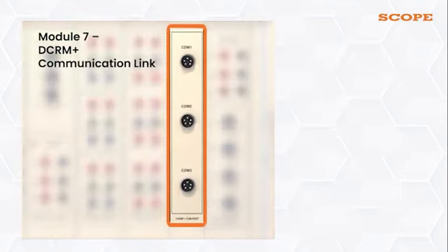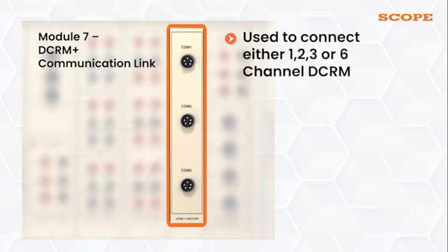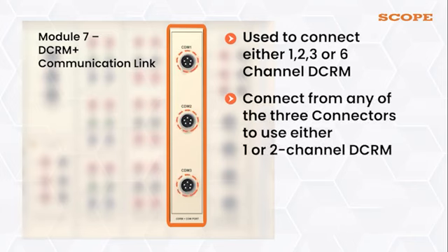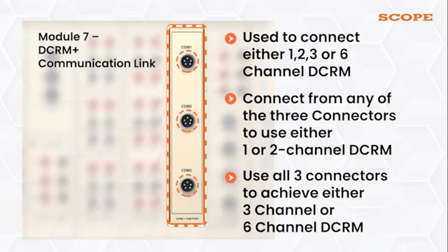Module 7. DCRM plus Communication Link Module. This is a very important module. It is used to connect either 1, 2, 3 or 6 channel DCRM. We can connect from any of the 3 connectors to use either 1 or 2 channel DCRM. Similarly, we can use all 3 connectors to achieve either 3 channel or 6 channel DCRM. All this is possible through the software.